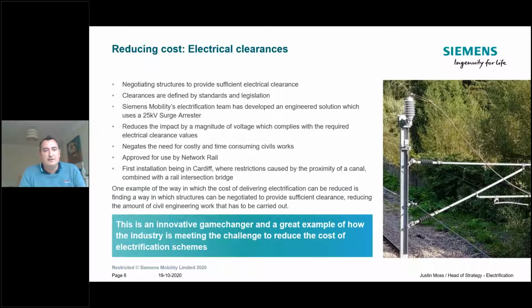In response to this, we've looked at an engineering solution such as surge arresters that work on a 25 kV network in circuit with the overhead line system. It enables reduced electrical clearances to be applied and delivers significant cost and delivery benefits. By introducing surge arresters into the electrification system at bridges and tunnels, if overvoltages do occur, for example through a lightning strike, the surge arrester reduces the impact by magnitudes of voltage, which complies with the required electrical clearance values between overhead line and structure. Depending on the required protection level, surge arresters can be applied to the overhead line equipment on both sides of the structure and for each contact system running through it, which reduces electrical clearance.